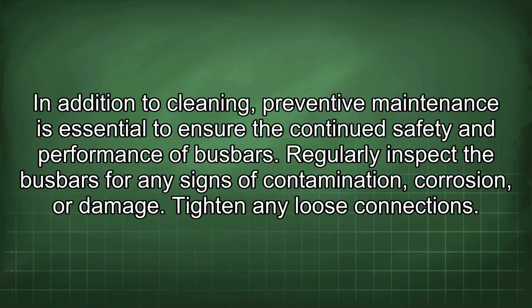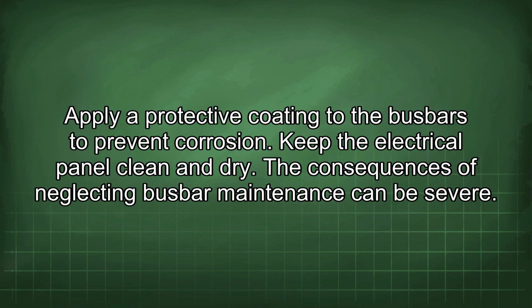In addition to cleaning, preventive maintenance is essential to ensure the continued safety and performance of busbars. Regularly inspect the busbars for any signs of contamination, corrosion, or damage. Tighten any loose connections. Apply a protective coating to the busbars to prevent corrosion. Keep the electrical panel clean and dry.